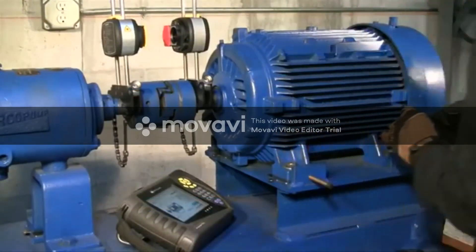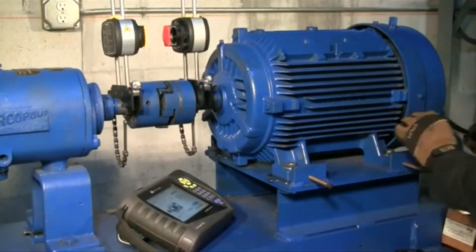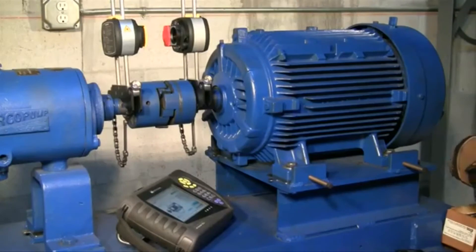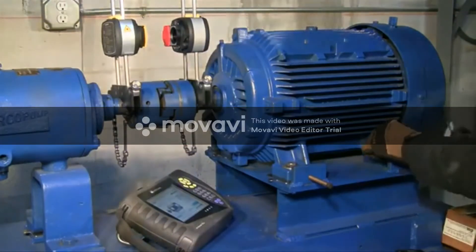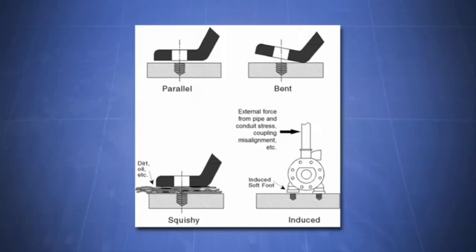If your soft foot values are greater than 2 mils, then you have a soft foot that needs to be addressed. Be aware that the numbers are not necessarily the actual gaps under the machine feet. When loosening and tightening the hold down bolts, we are measuring the effect of that particular foot on the shaft deflection, not the actual gap. If soft foot was detected, we will then measure the true gap under those feet using a feeler gauge. With this technique, we can determine the exact soft foot condition, such as a parallel air gap, bent foot, or deflecting base.